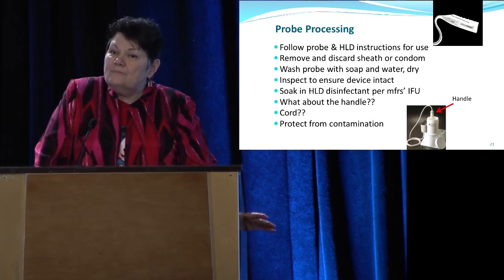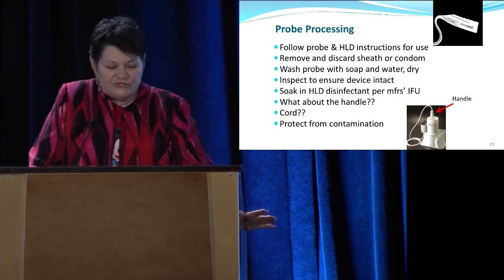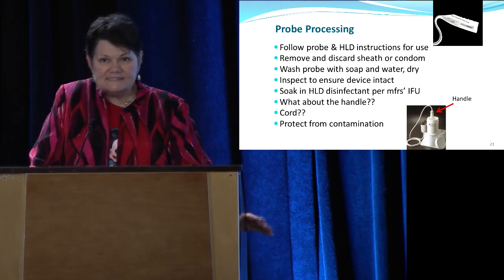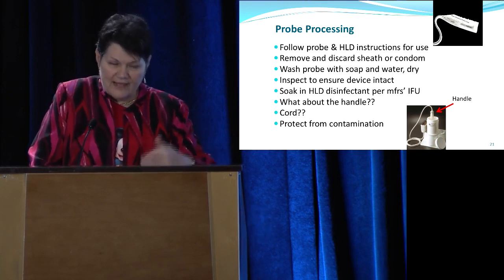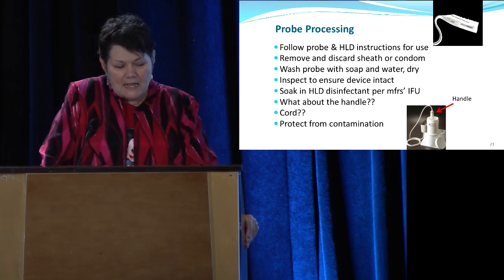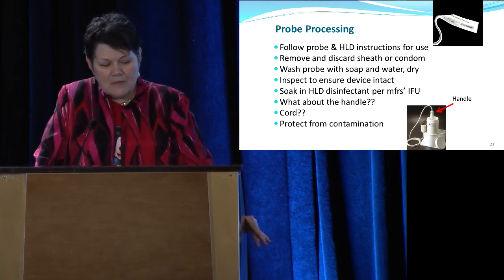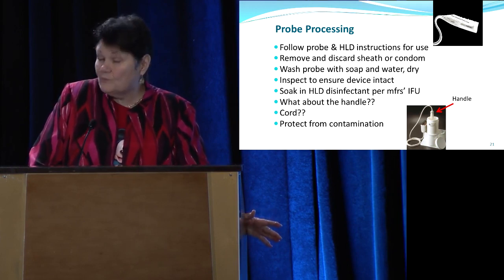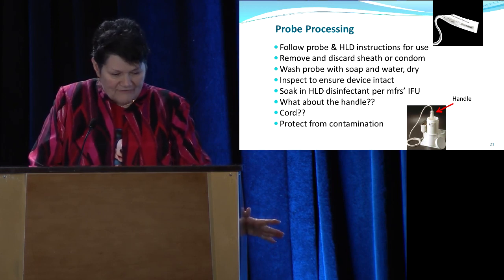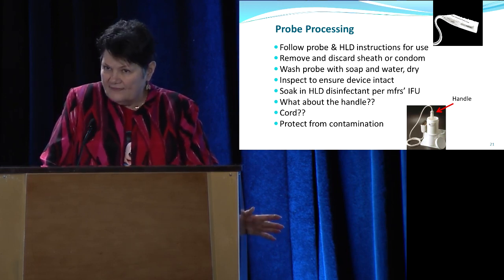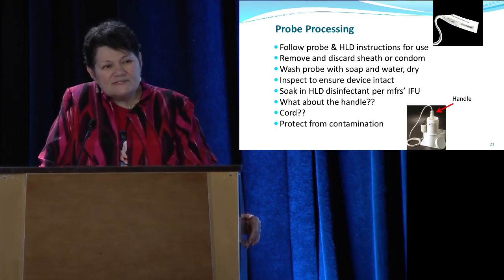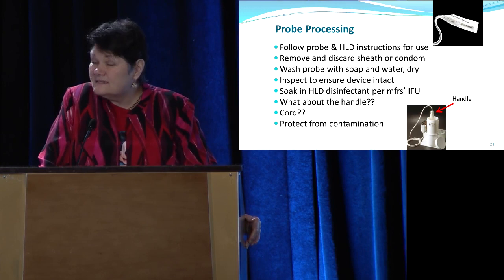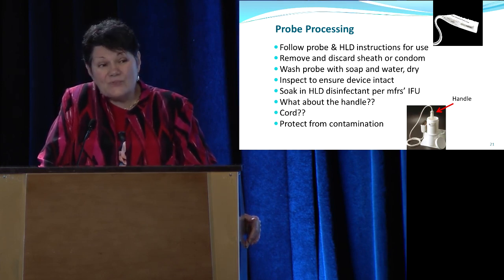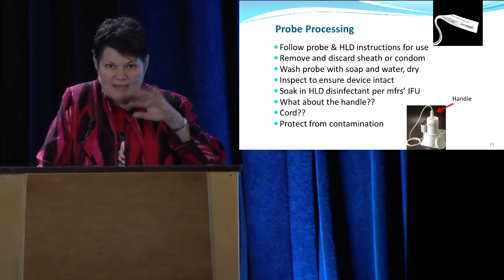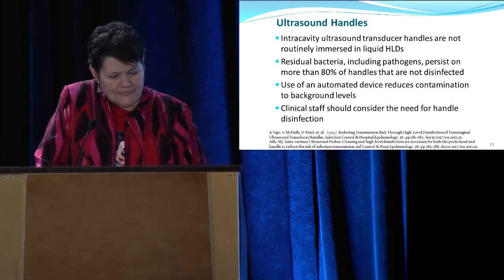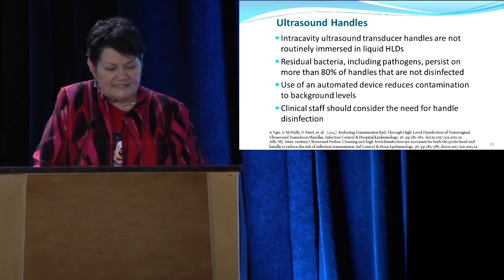So you need to follow the probe instructions for cleaning and disinfection. You need to follow the high-level disinfectant instructions. So if there are conflicts there, you need to look at other high-level disinfectants or talk to manufacturers. Remove and discard the sheath or condom, wash the probe, and often it says wash with soap and water. Some say wipe down with a low-level disinfectant, whatever yours says, and then soak in the high-level disinfectant, as we've talked about. And we've also mentioned the handle may be contaminated, so ideally your probes would be fully submersible so that you can disinfect the handle as well. And I'm going to talk about another thing as well here as we go on. And again, once it's done, you want to protect it from contamination.